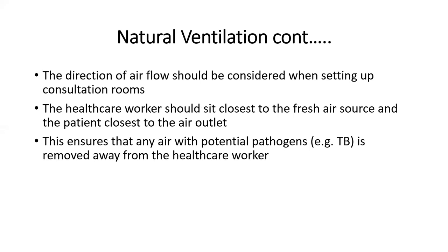That is the design of the consultation room. The healthcare worker should sit closer to the fresh air source and the patient closer to the outlet. This will ensure any air with potential pathogens, e.g. TB, is removed away from the healthcare worker.